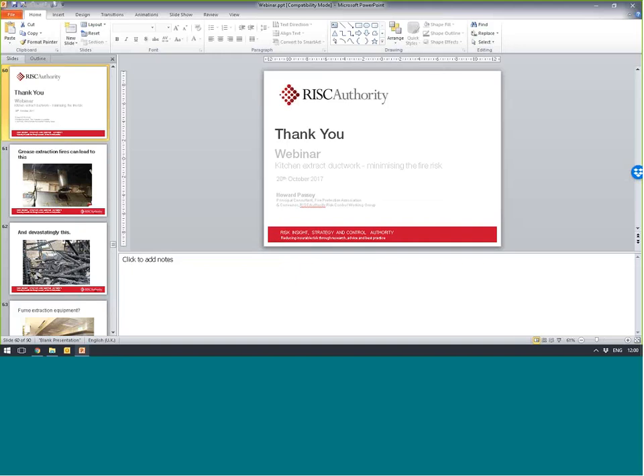This is more of a statement than a question from Alan Beattie. He states that too often we are submitted cleaning certificates stating the ductwork has been cleaned in accordance with TR19. But instead of taking a certificate at face value, you often find on the cleaning report that large elements of the ductwork are inaccessible.